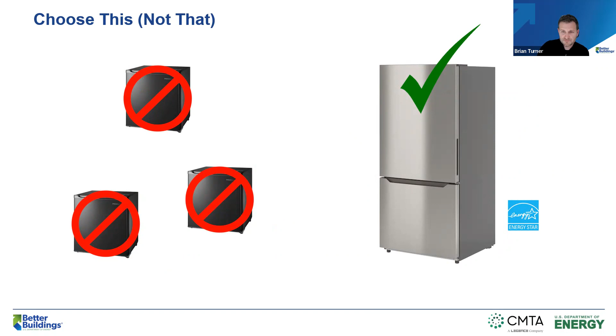Here's another quick example. In our office building, we had a vending service briefly, and they brought in the oldest Pepsi machine I think I'd ever seen, at least from the 80s. It seemed to run nonstop, made a lot of noise, generated a lot of heat in our break room, and never turned off. I put a kilowatt meter on it, came back a couple days later, and confirmed that this Pepsi machine never turned off its compressor in something like 72 hours. We got rid of it shortly afterward, and actually moved away from the vending model entirely, which we should have done long before. The better alternative is an Energy Star rated vending machine, potentially with an add-on vending miser, which adds occupancy controls for savings in after-hour situations while still taking care of the product.